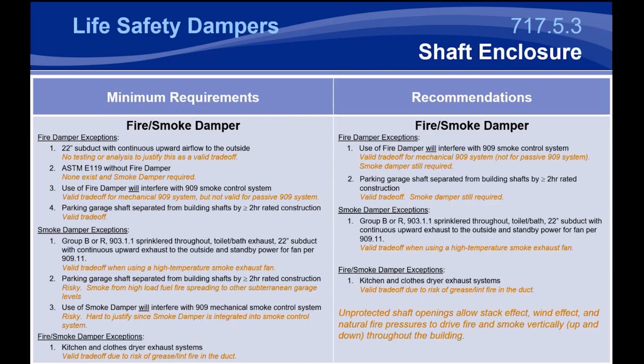We're not going to talk about the ASTM E119 trade-off again. One thing we will talk about is some of the differences when using what's called a 22-inch subduct. So this is something that's specific to shafts. If you've got a 22-inch subduct where you have either an exhaust shaft or a supply shaft, typically it's used for exhaust shafts, but if you've got an exhaust shaft where that subduct is actually turned up and extends 22 inches up into the exhaust shaft, and it has continuous airflow to the outside, you can remove the damper from that shaft wall. That's typically the only way to use that subduct, in exhaust shafts.